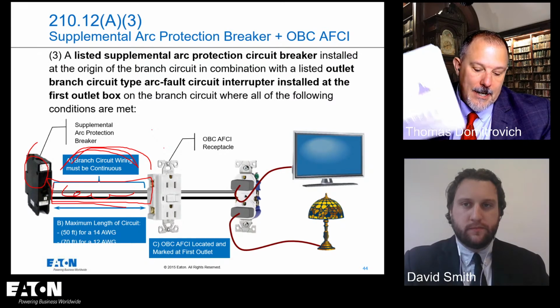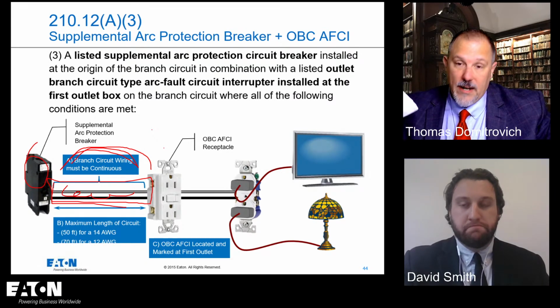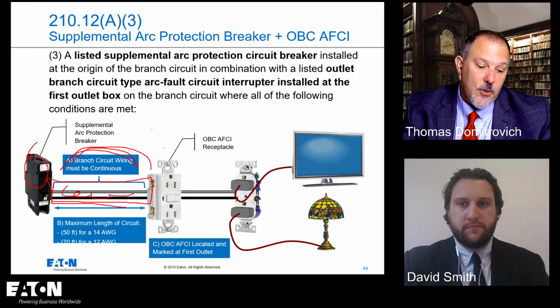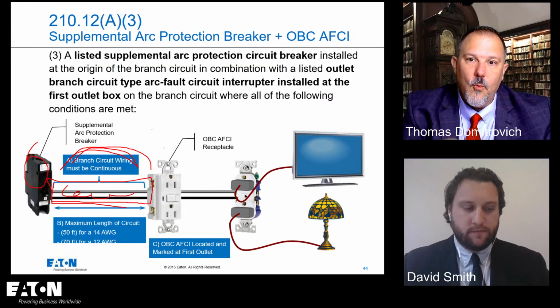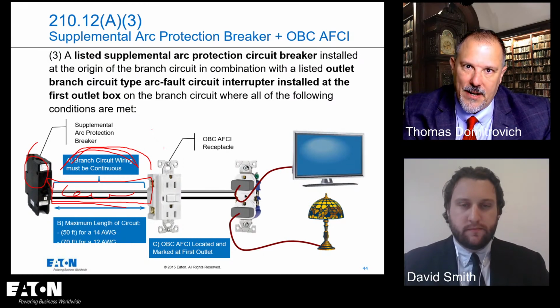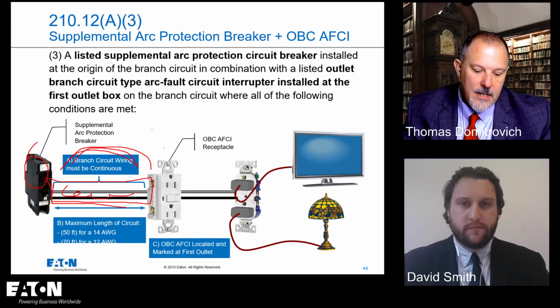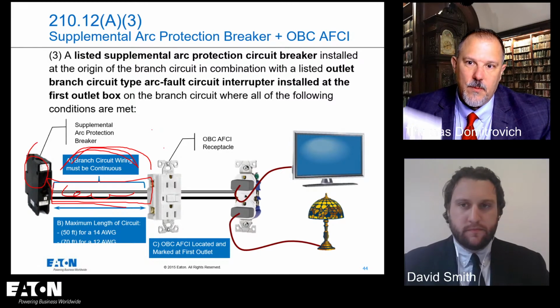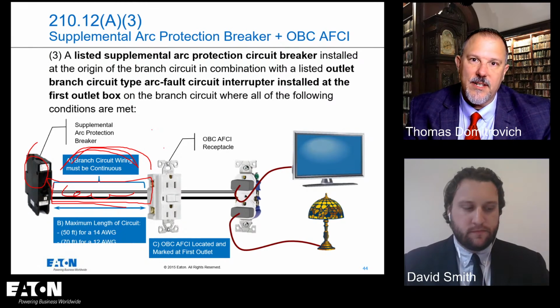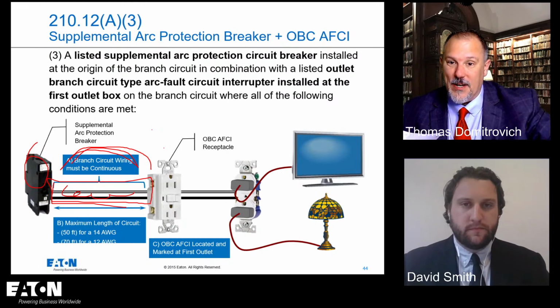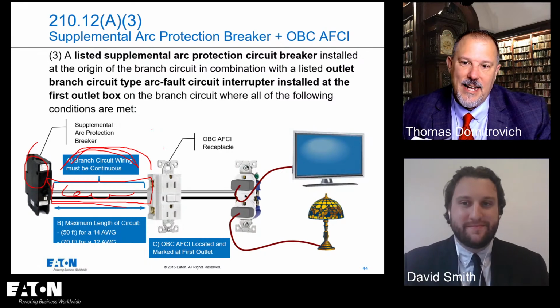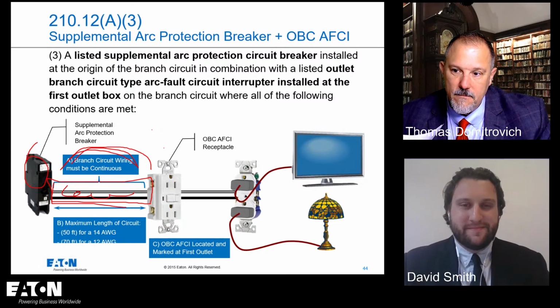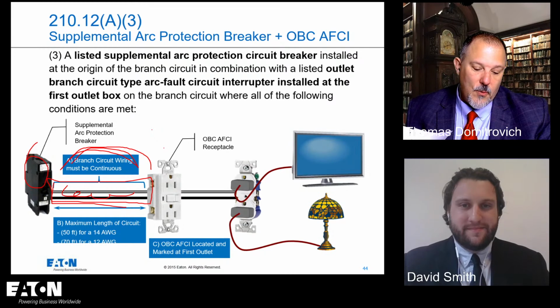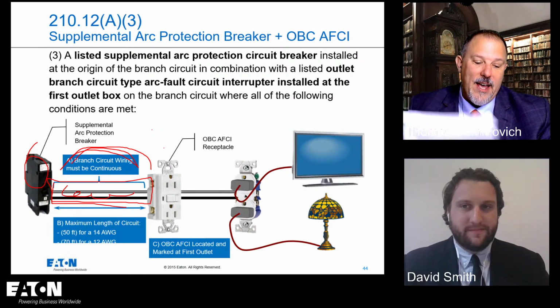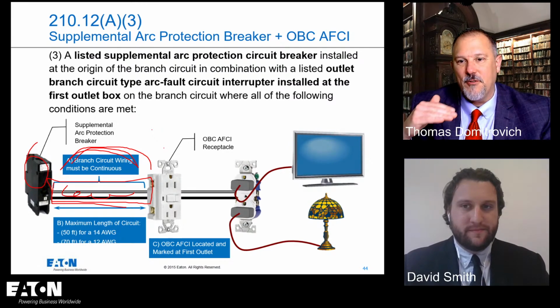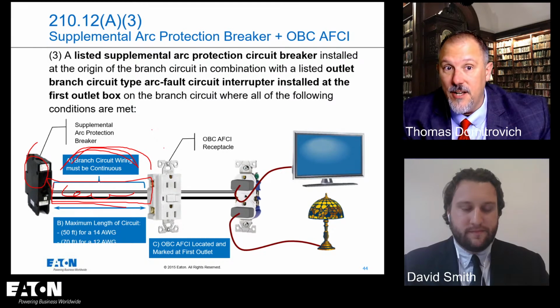So it's still a 20 amp thermal mag 489 device. Mm-hmm. So the study looked at what are the typical instantaneous pickup values for circuit breakers. They came up with an equation to replicate the arcing, which was available fault current was the other one. And what UL 1699 uses is 500 amps, right? And so you have a minimum available fault current of 500 amps at the service, which was argued, right?